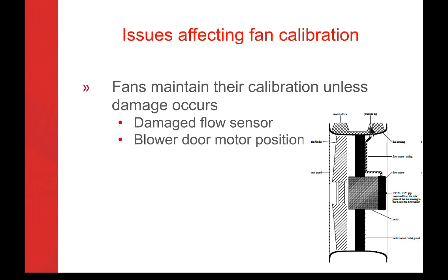And then the flow sensor, you can connect a tube to the tap, suck on it, and it should hold a vacuum. You can check for that by it sticking to your tongue for a couple of seconds, showing that it's holding a vacuum. If it doesn't, the way I troubleshoot it is this: here's the flow sensor, and there's a tube coming off of that, and then there's a 90 degree turn that's barbed. You can unplug that tube going to the flow sensor, and that tube is part of the flow sensor, so it shouldn't be coming out, shouldn't be loose, you shouldn't be able to pull it out. You can disconnect it and do that test again on just the flow sensor part. If that fails, you'll need to get a new flow sensor. If that passes, then it's something in the other tubing connection.